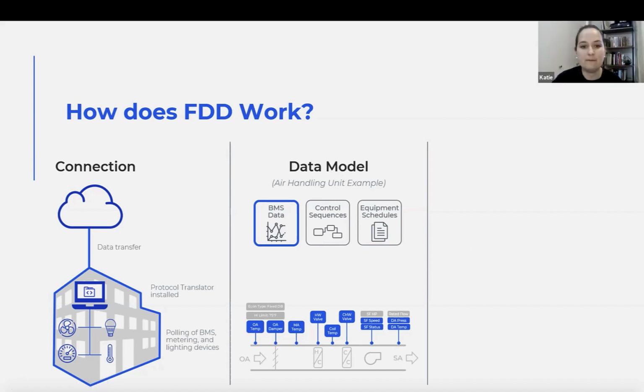And then your FDD provider will input the control sequences, so what it would expect your system to do, into your fault detection and diagnostics program. Then it lives there real time, live, and it knows. The example given here is how your economizer works. What are your high limits, and how is it controlled? And then it'll take those equipment schedules. So how big is my fan and what's my rated flow? That's instrumental in deciding cost, right? It uses that to determine how much this is going to cost me to fix, and how big of a comfort impact potentially it is going to be. How big is my equipment? So it'll create this data model.